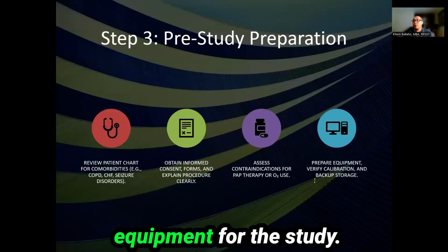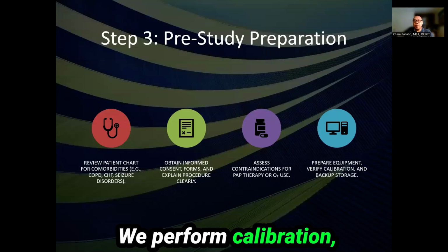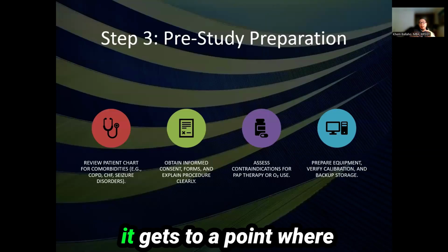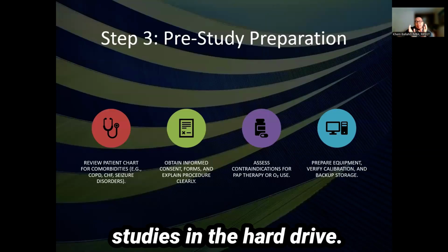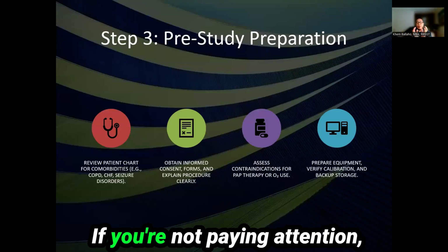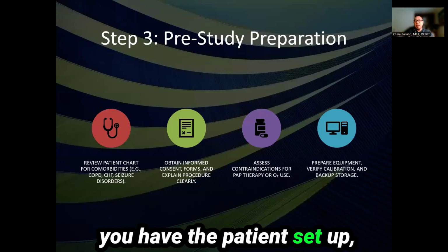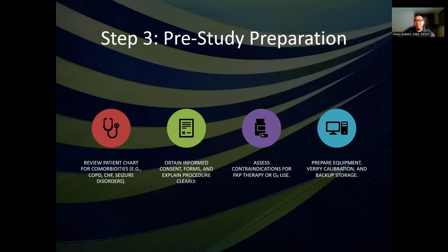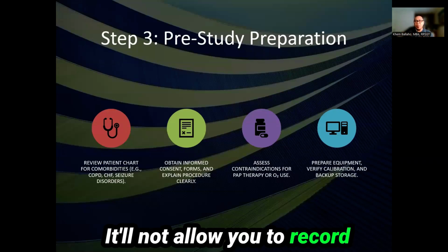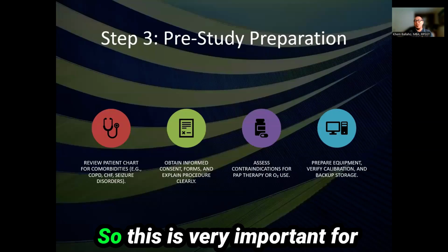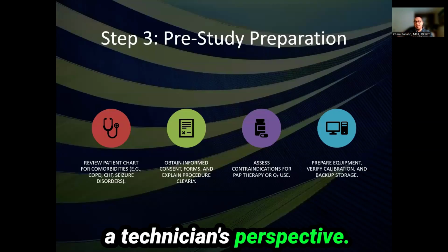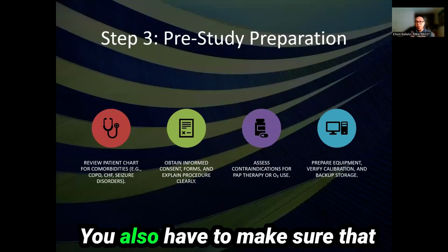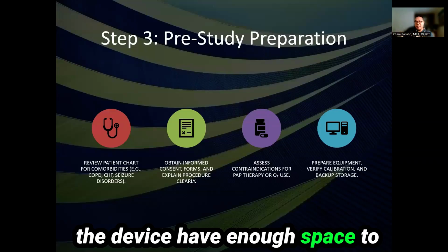And then lastly, prepare equipment for the study. We perform calibration and we make sure that we create a backup storage. And this is important because it gets to a point where you have so many sleep studies in that hard drive. If you're not paying attention, you have the patient set up, you're ready to go, and then you start recording. And then what happens to the device? It stops. It will not allow you to record because the hard drive is full. So this is very important from a technician's perspective. You always have to check if your equipment is ready for recording, meaning you also have to make sure that the device has enough space to record.